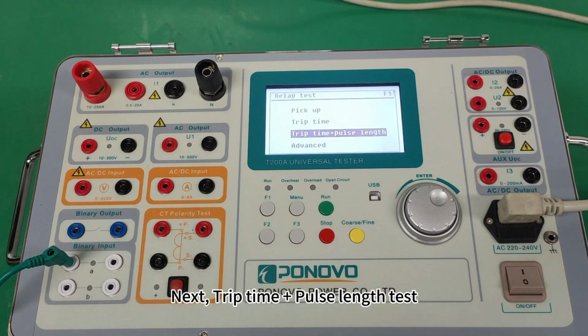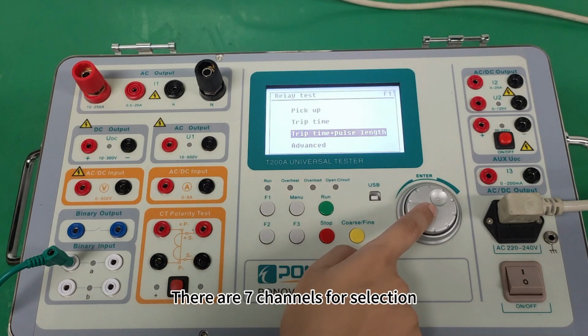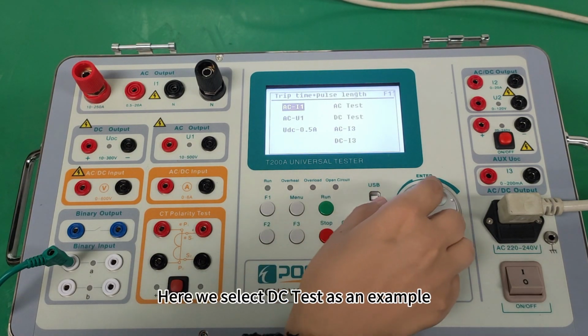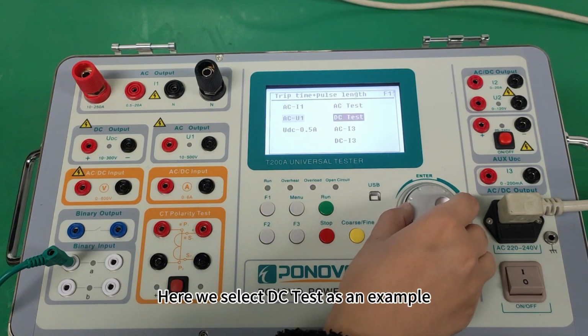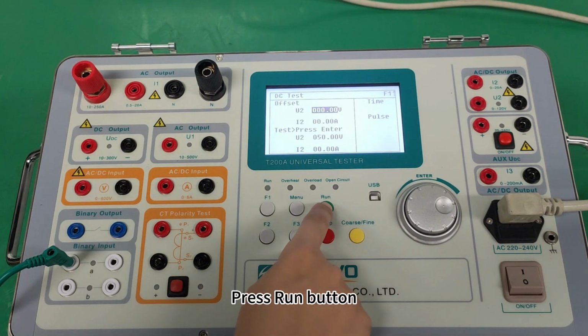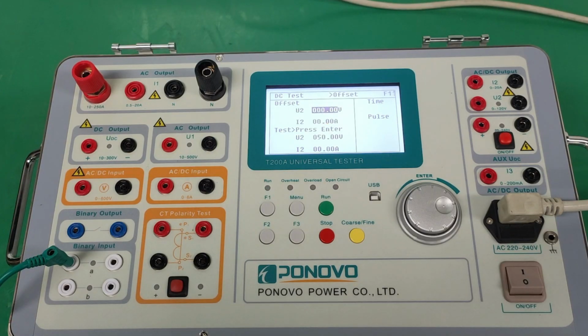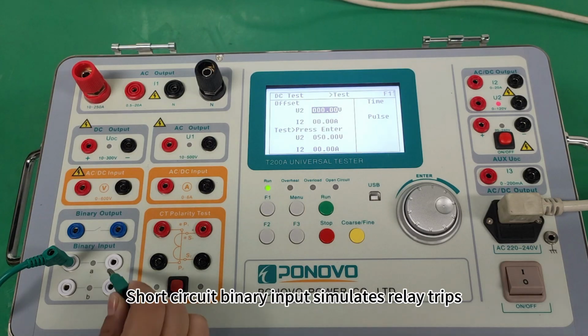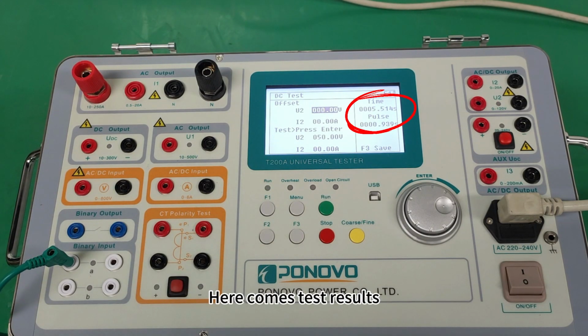Next, trip time plus pulse length test. There are 7 channels for selection. Here we select DC test as an example. Press Run button. Then output offset value. Press Enter button. Then output test value. Short circuit binary input simulates relay trips. Here come test results.